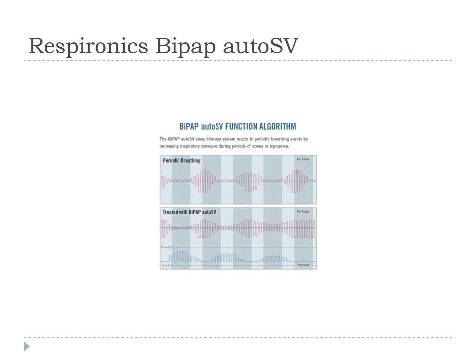And so at the start of this titration, you see the patient takes some deep breaths, and then it starts to wane, and they start to take shallow breaths. During the shallow breaths, you see the pressure increase during those times. And then the patient continues to take some shallow breath. Eventually they take some bigger breaths. As the patient takes bigger breaths, the machine's pressure drops back down to let them breathe normally.